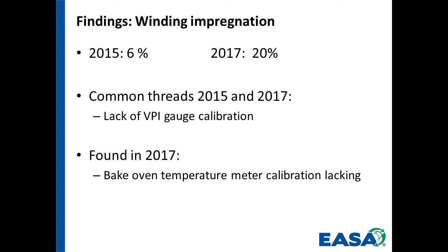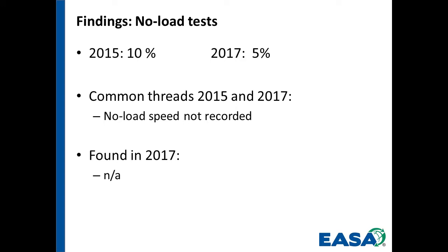Also, in 2017, a bake oven temperature meter calibration was lacking. So that word calibration seems to be another common thread. No load testing. Not that it was a big issue, but the thing that stood out was the no load speed not being recorded. You have the digital tachometer, but it wasn't recorded on every job. That's probably an important thing: have it as part of your repair record form, a line item entry that you have to fill out. If it's there and you know you've got to fill it out, it's going to happen.